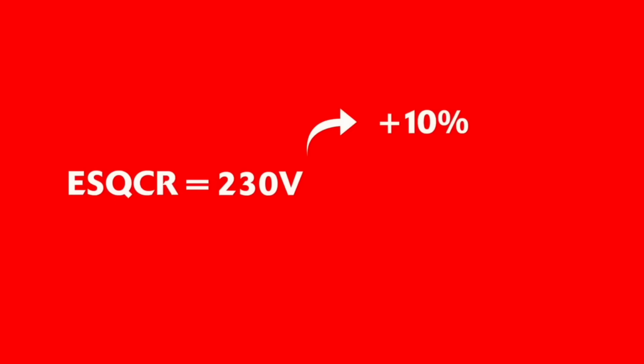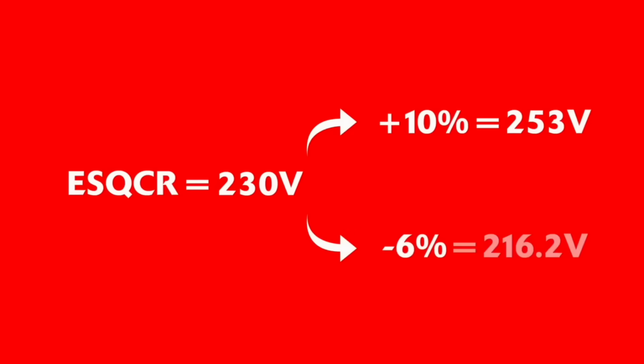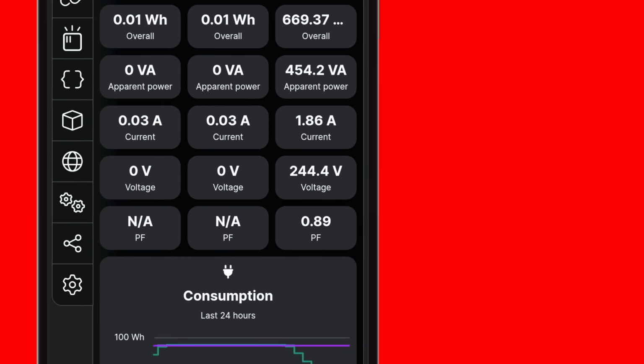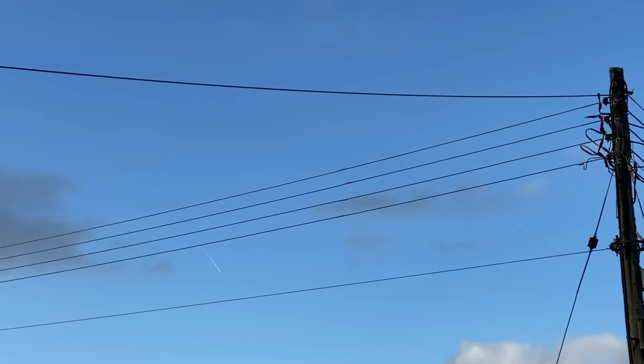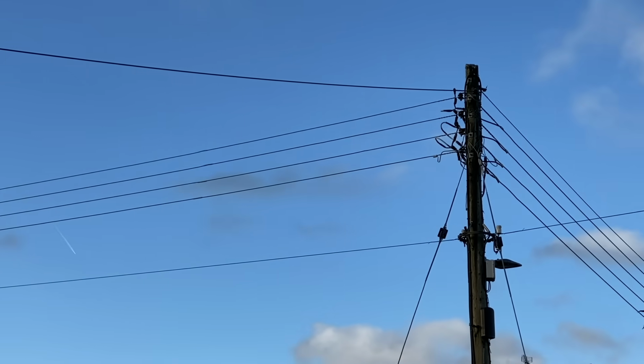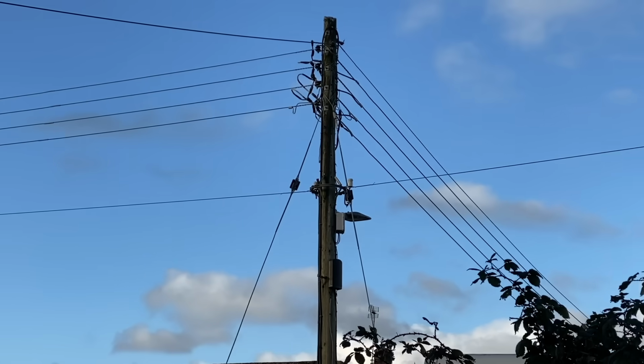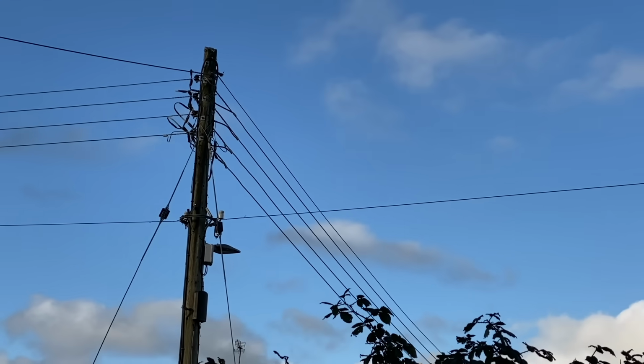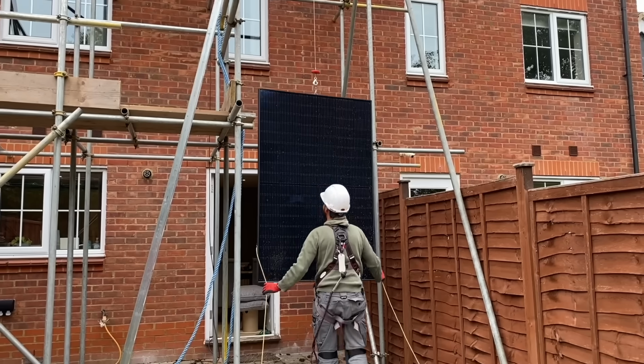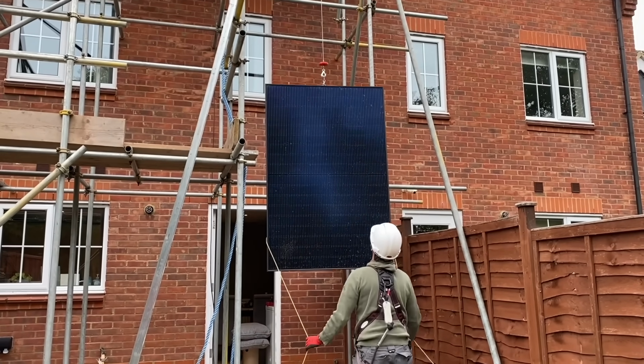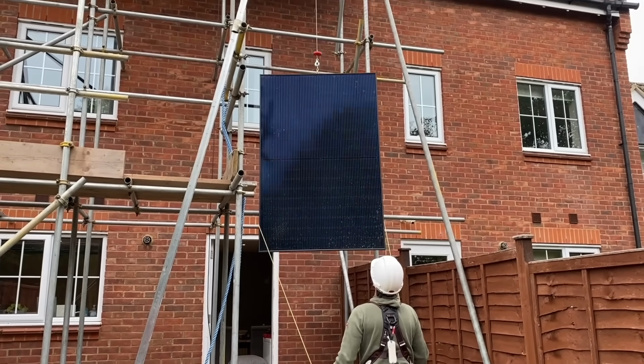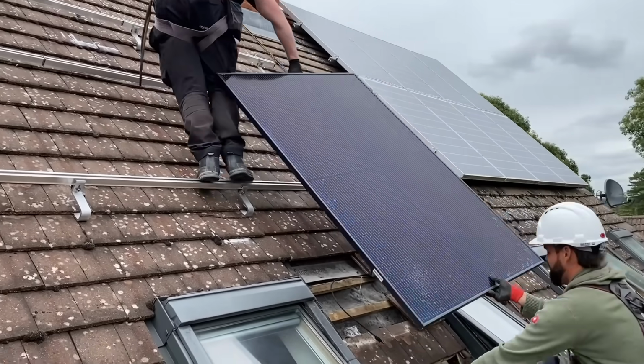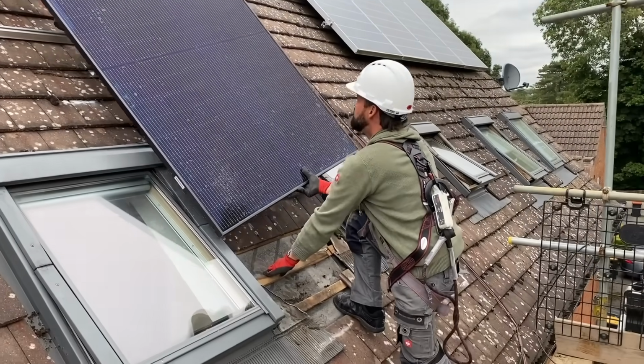At present, UK mains voltage is nominally 230 volts with a tolerance of plus 10% and minus 6%. This standard was adopted in 1995 to harmonise with Europe, though in practice most households still experience close to the old 240 volts. The new proposal would extend the lower tolerance to minus 10%, allowing voltages as low as 207 volts. Network operators say this would enable them to reduce average grid voltages by around 2%, or 5 volts, freeing up capacity for more renewable generation. It's expected that they will reduce the voltage initially by 1% and then, following an assessment, cut by a further percentage point. However, lowering the limit could have side effects.